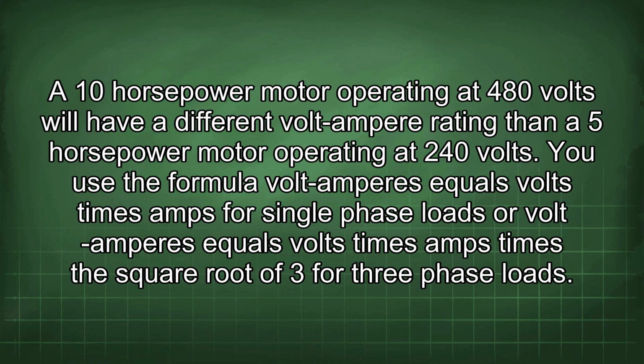A 10 horsepower motor operating at 480 volts will have a different volt-ampere rating than a 5 horsepower motor operating at 240 volts. You use the formula volt-amperes equals volts times amps for single-phase loads, or volt-amperes equals volts times amps times the square root of 3 for three-phase loads.